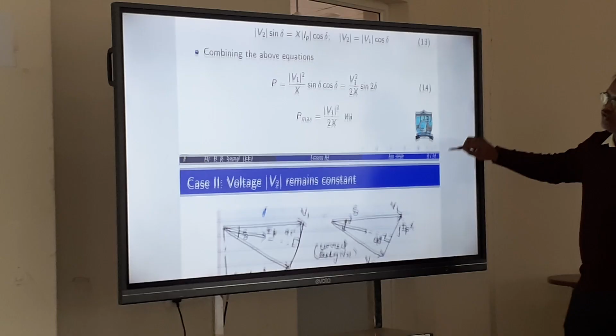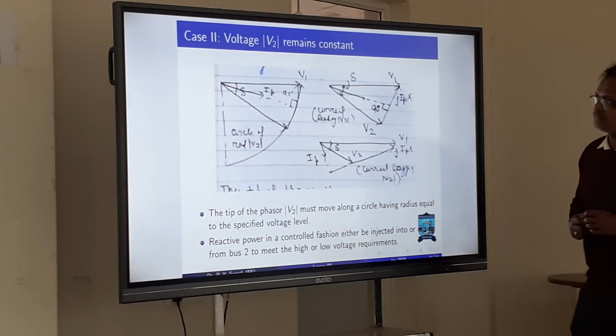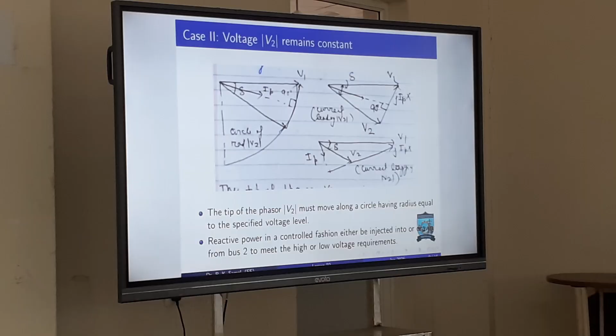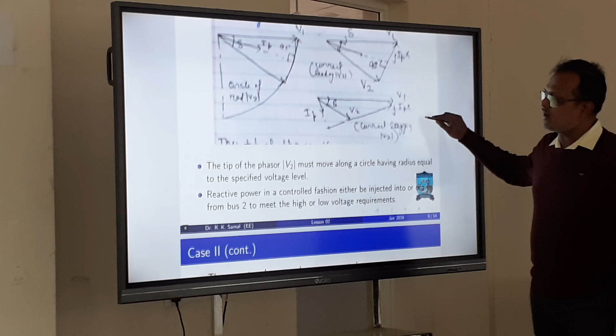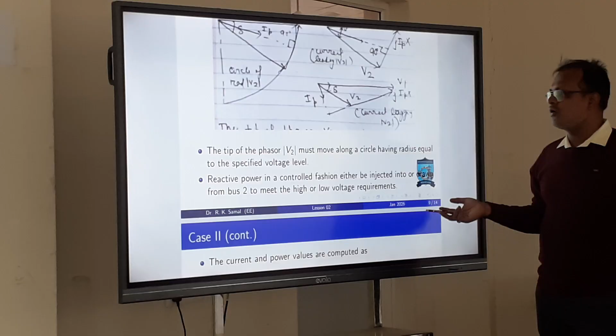Case 2. Voltage V2 remains constant. Which is an ideal case because we always want the receiving end voltage to remain constant. Otherwise that will affect the loads. So here what are the various things? The tip of the voltage phasor V2 must move along a circle having a radius equal to the specified voltage level. For this, reactive power in a controlled fashion must either be injected from bus 2 or absorbed to meet the higher voltage requirement. Reactive power is injected.